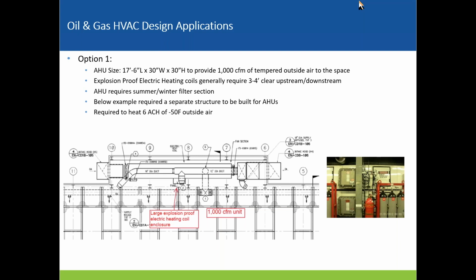So in this example, we had to build a separate structure on the side of the module just for the air handling unit itself. And you can see how it kind of shoehorned in here with the structure. You don't really have great access to the control panel or anything in this example. And you're required to heat the full 6 air changes per hour of minus 50 degree air.